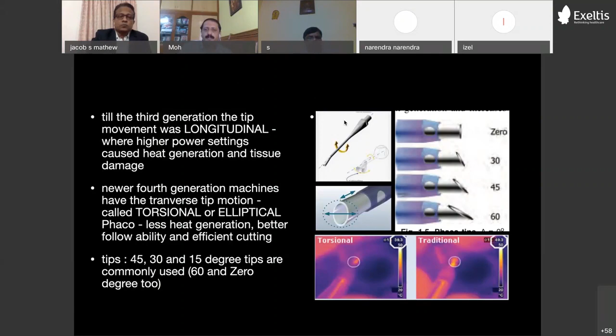And sleeves, as I mentioned, actually cover the tip of the phaco probe, an accessory to sort of insulate the wound. Otherwise, the wound gets cooked and burned. And so it's like a pathway for the fluid to pass over the tip and cool it. And it has got two side ports through which the irrigation fluid comes out, and the tip has a hollow inside, so the fluid aspiration occurs through the central hollow part of the tube. This fluid insulation is basically to safeguard the wound.